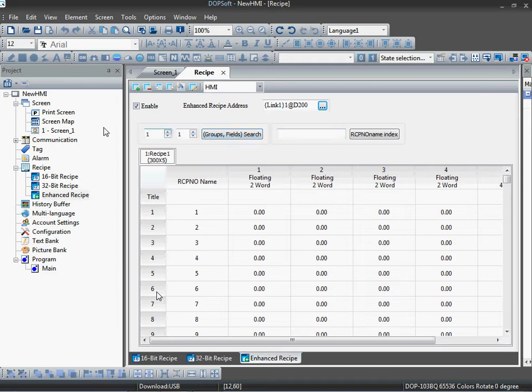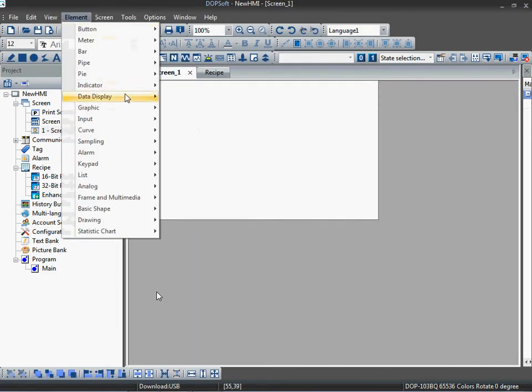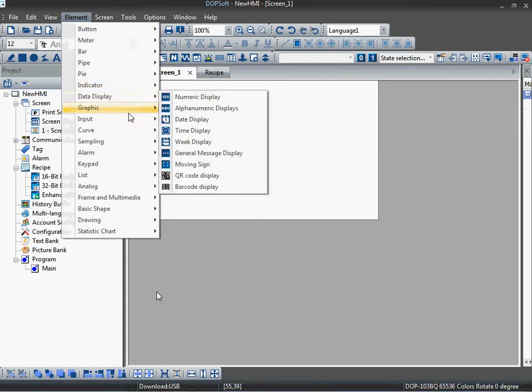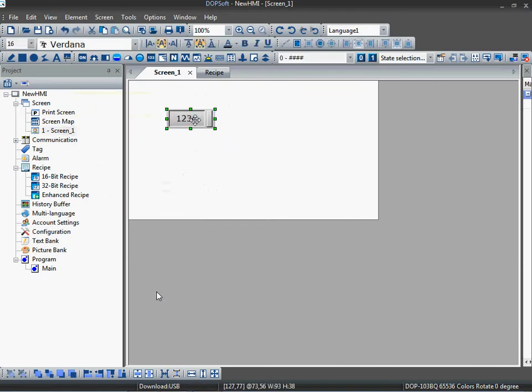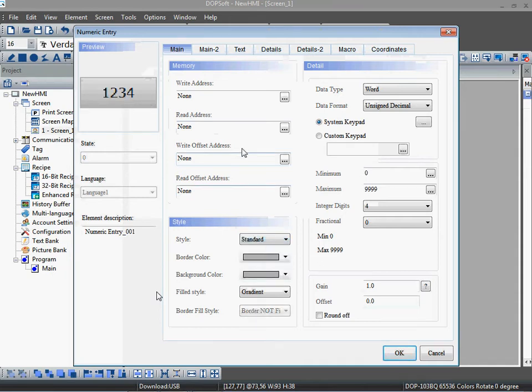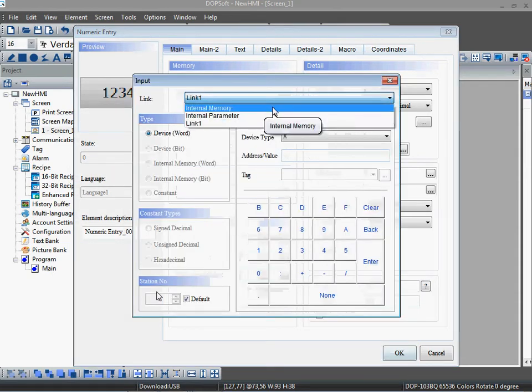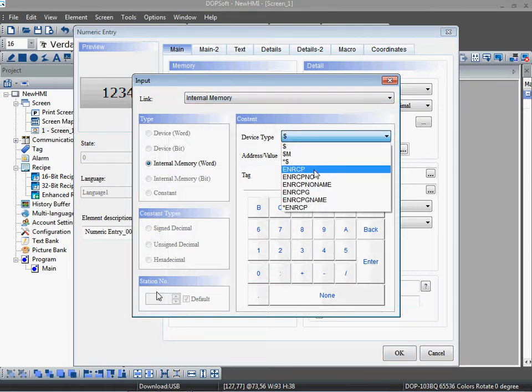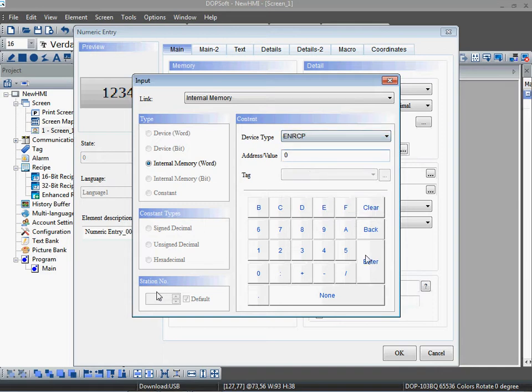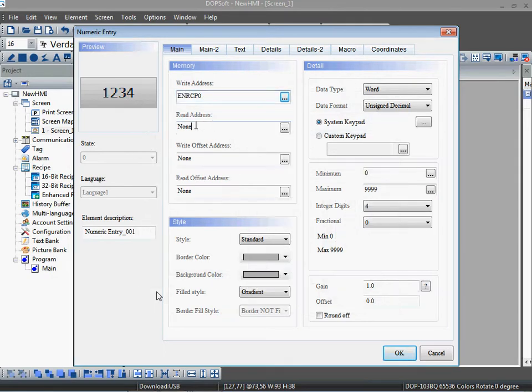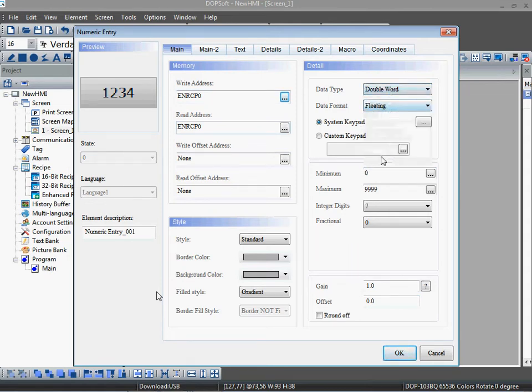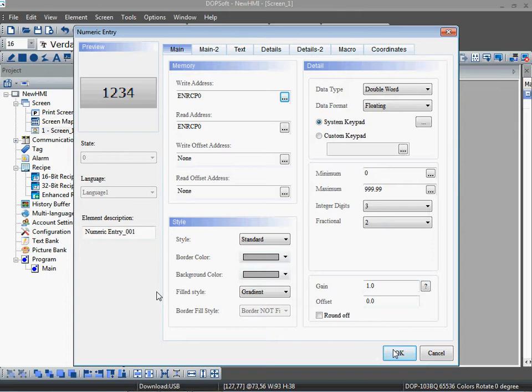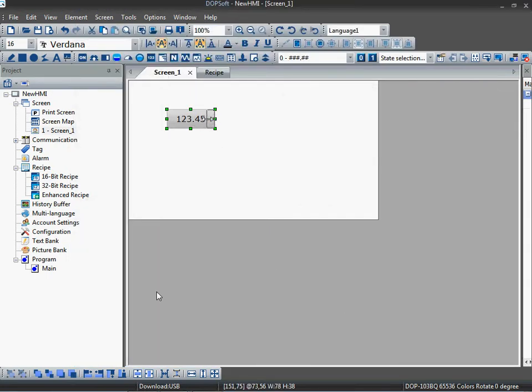Okay, now let's start. Go to element, take one numeric input. Okay, just give the address. Here you have to select the address as Enhance Recipe 0 — go to internal memory, enhance recipe. Remember this: the first address would be 0. Copy that and enter the same address in read address. We want floating, so change the word to floating. I will define the format as 999 maximum value, integer digit 3 and fractional digit 2. Okay, let's finish this.